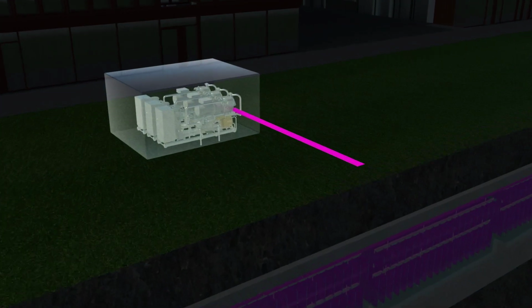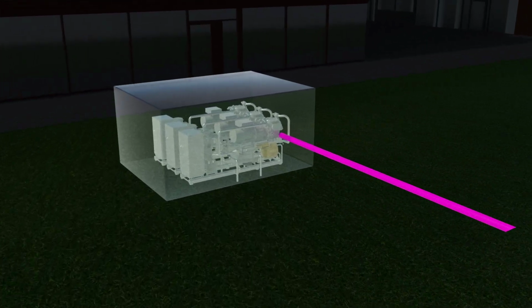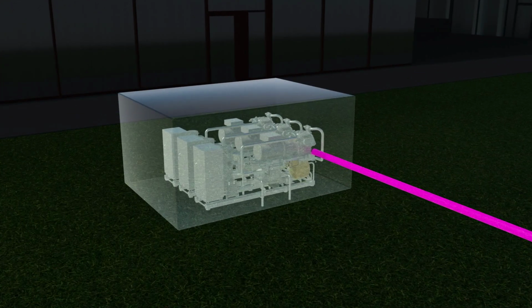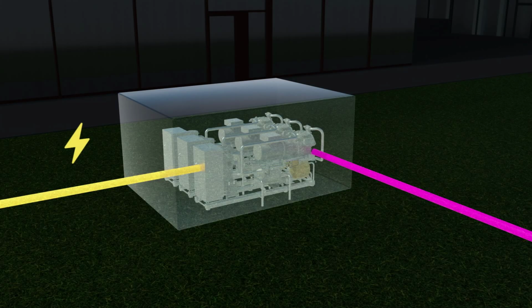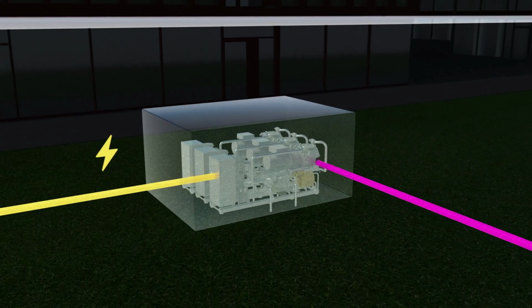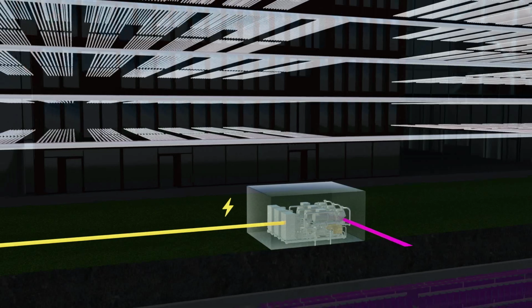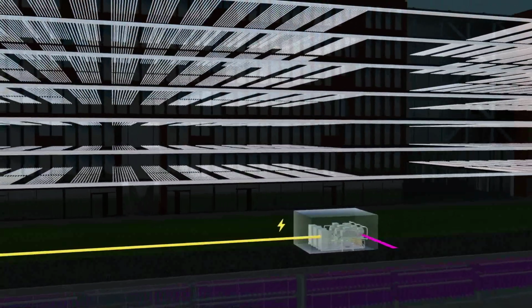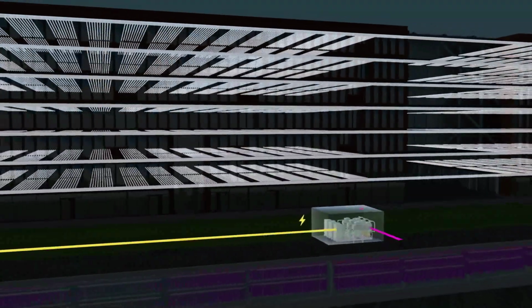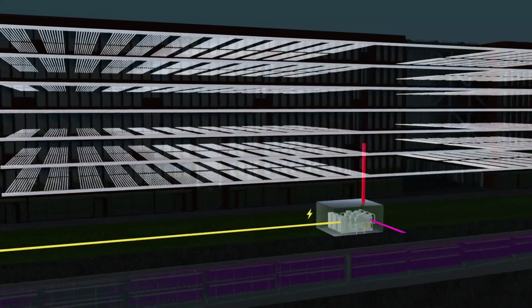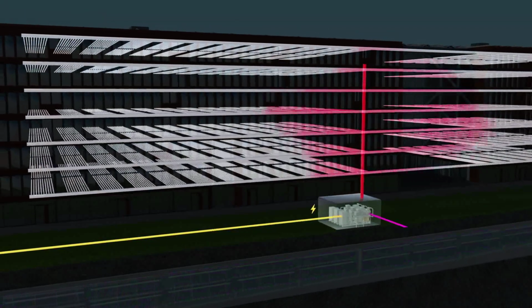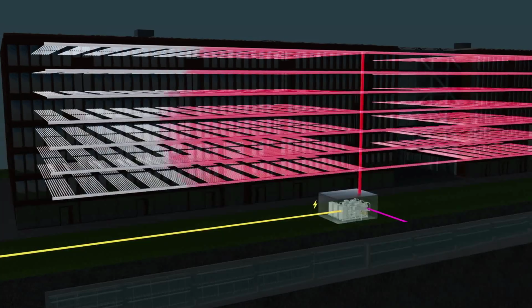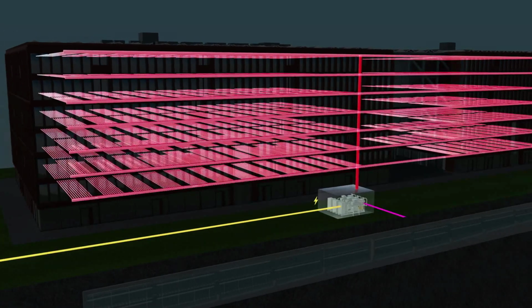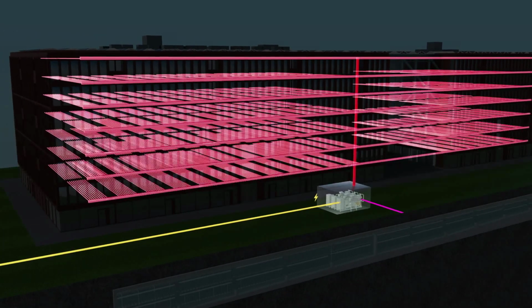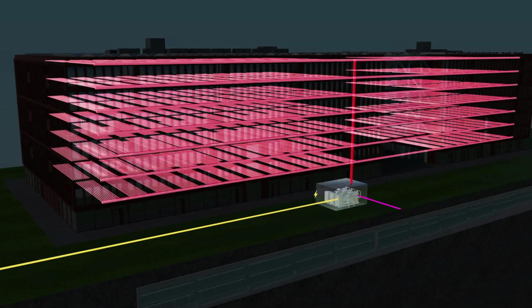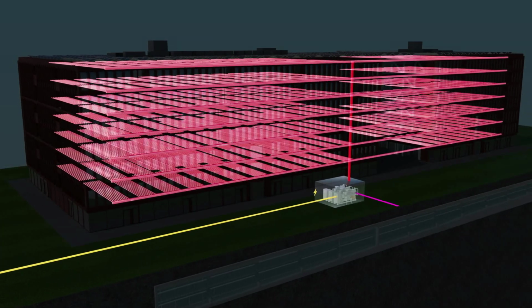The heat pumps use this energy. Running on electricity, they bring up the temperature of the water in the storage tank from around 20 degrees Celsius to that of heating water. Radiant ceiling panels in the offices, as well as other heat exchangers, keep the building at a pleasant temperature. Due to the large amount of heat in the storage tank, green electricity can be used very efficiently for heating. At the same time, the water in the storage tank continues to cool down.